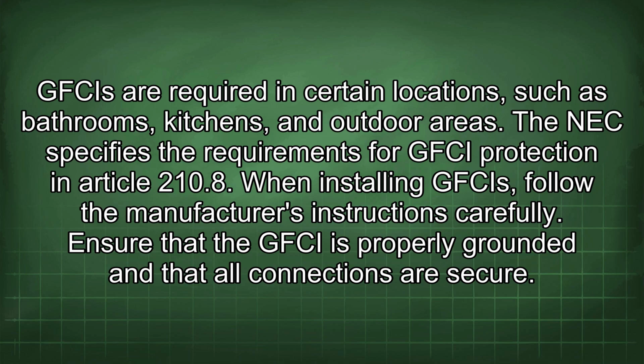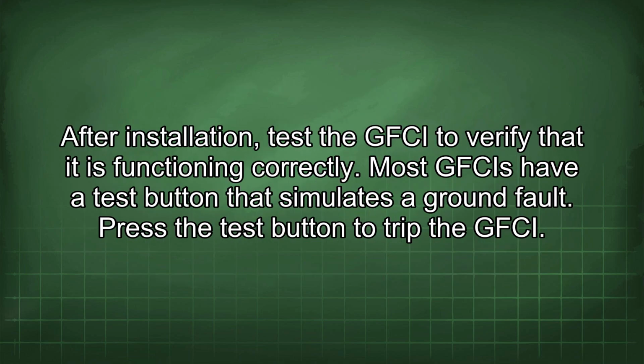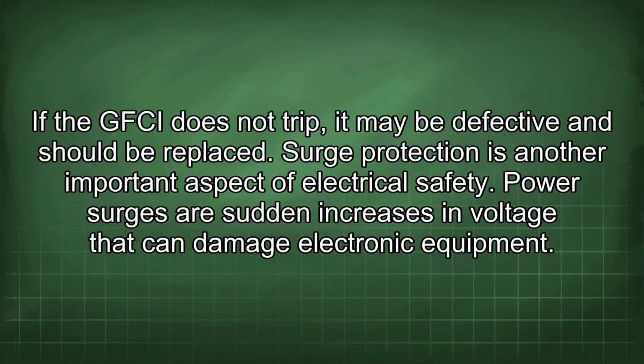When installing GFCIs, follow the manufacturer's instructions carefully. Ensure that the GFCI is properly grounded and that all connections are secure. After installation, test the GFCI to verify that it is functioning correctly. Most GFCIs have a test button that simulates a ground fault. Press the test button to trip the GFCI. If the GFCI does not trip, it may be defective and should be replaced.